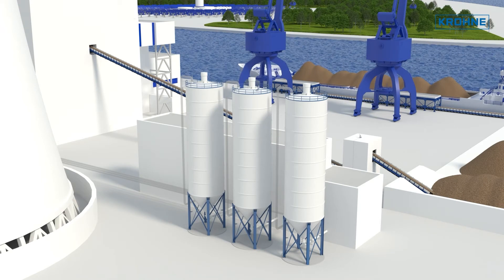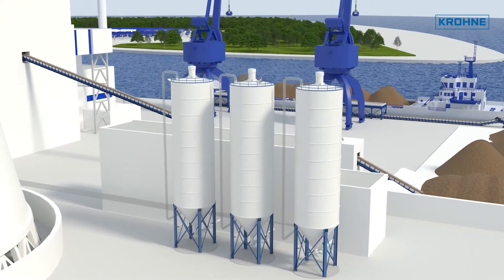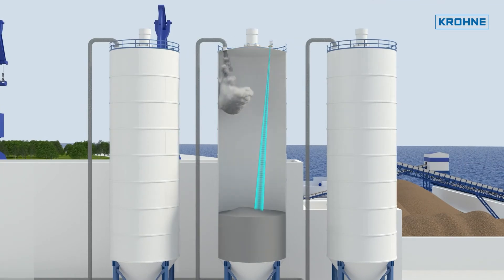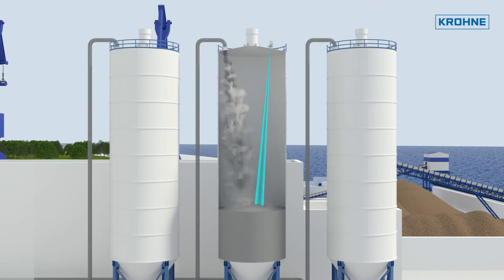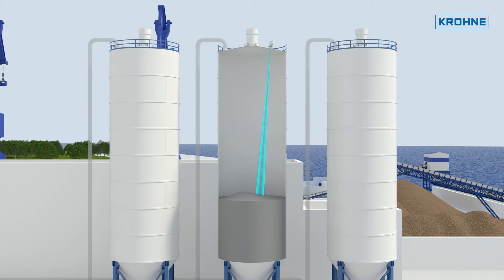Conveying usually takes place at intervals with a blast of transport air. Buildup in the delivery line is prevented by high flow velocities. The fly ash falls down into the silo, and the excess transport air escapes into the atmosphere via a filter. The filling and management of the various silos is monitored and controlled via continuous level measurements.